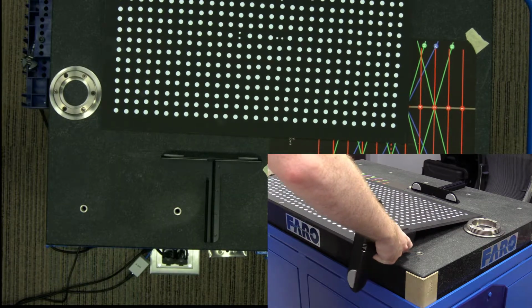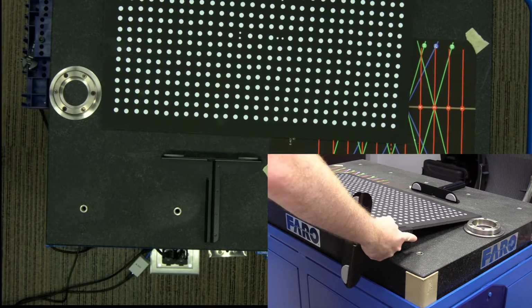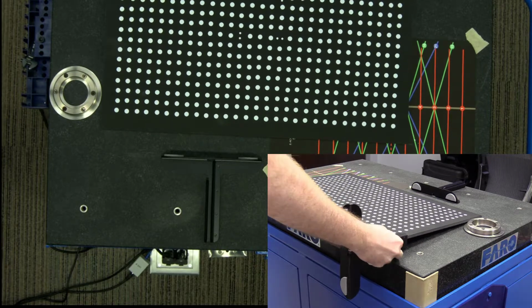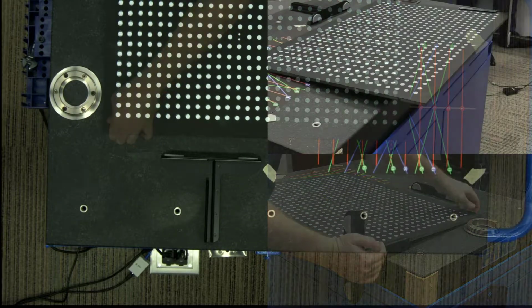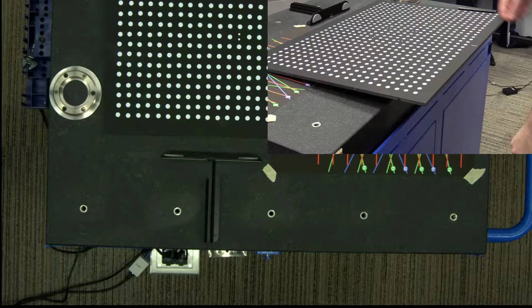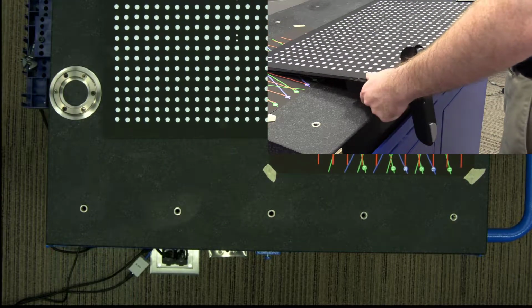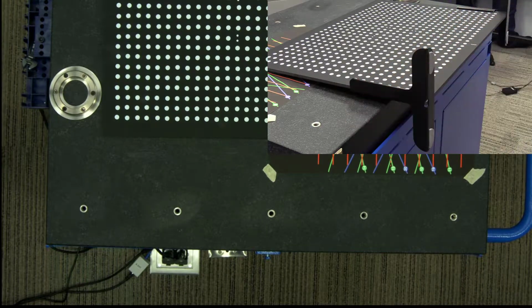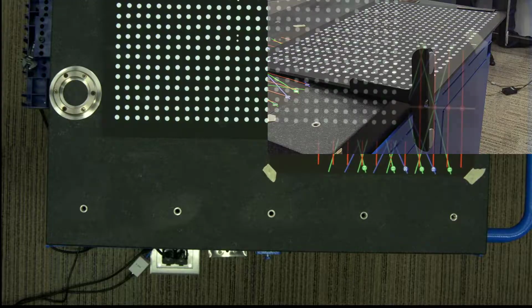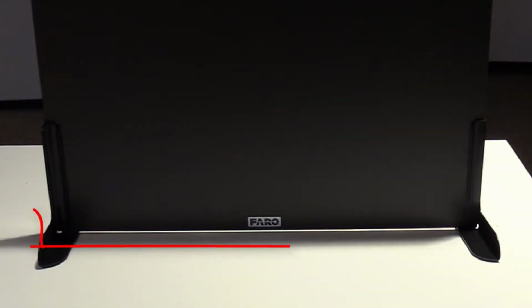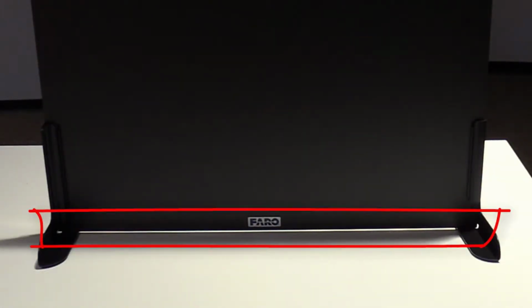The serial number of the plate is at the top. Note, when putting on the stands, a minor amount of force may be needed to put them on. However, take careful note to ensure you don't touch the white dots of the calibration plate. Ensure that each calibration plate stand is flush on both sides, and when the calibration plate is raised to sit on the table, that the bottom of the calibration plate is flush with the calibration plate stand.